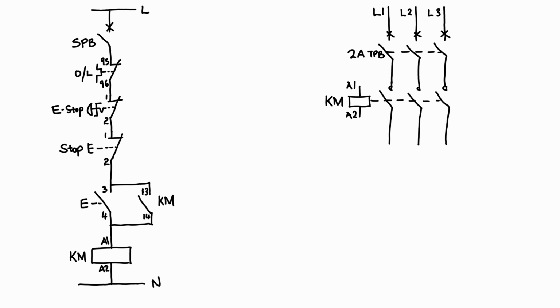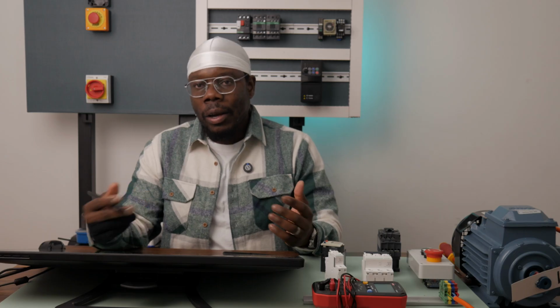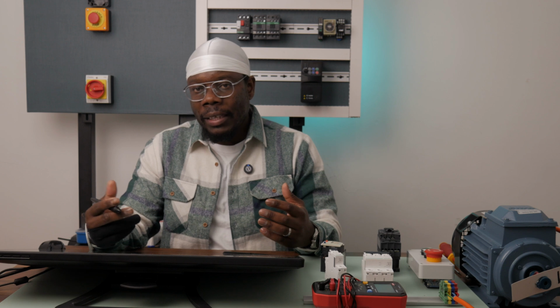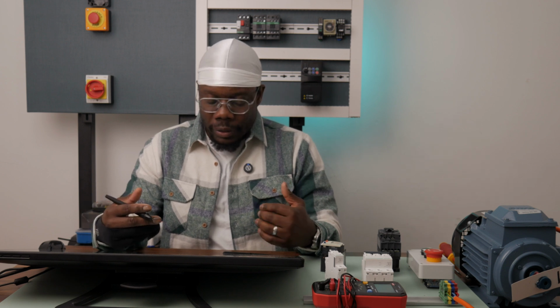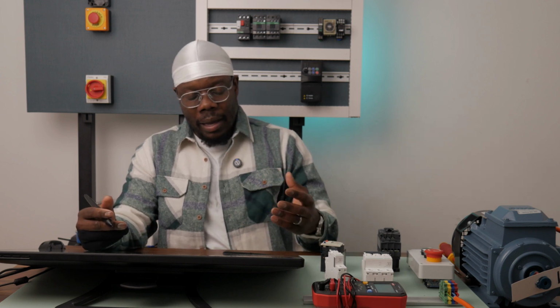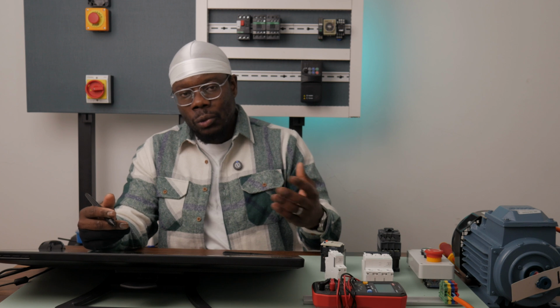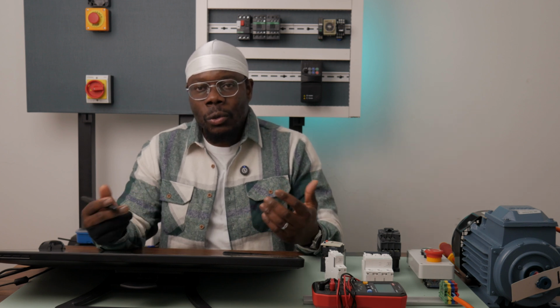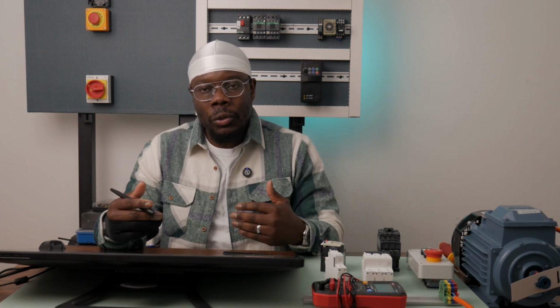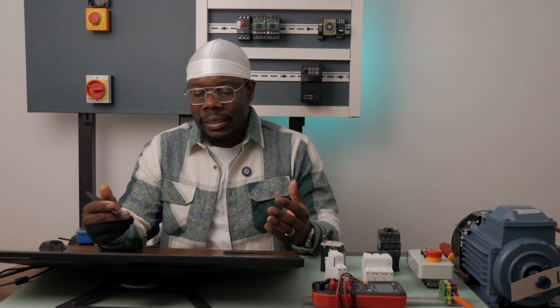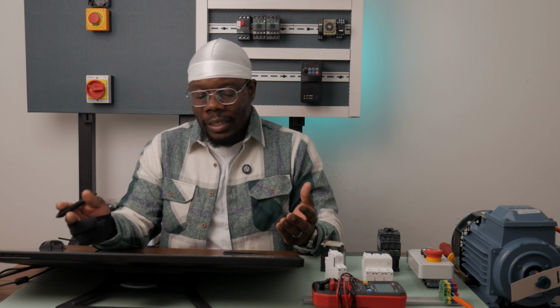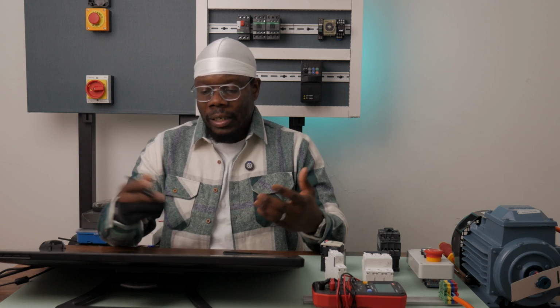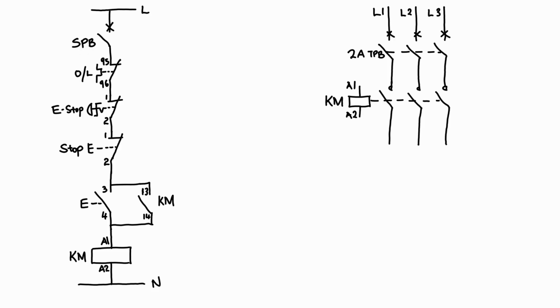If you've got several contactors in your circuit, you're going to need a way of labeling and identifying those contactors. So you label them KM1, KM2, and so forth, so that someone who looks at your circuit is able to make sense of your schematic. Here there's just one contactor, so that's the reason why I just labeled it KM. This is the same contactor coil appearing in different places, but it's the same contactor coil.